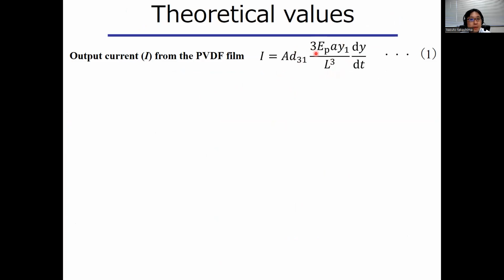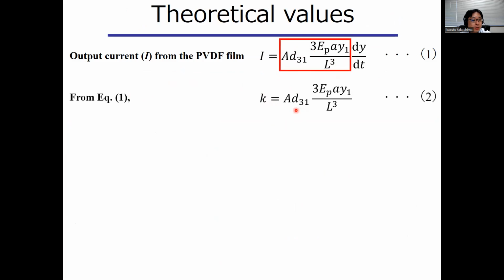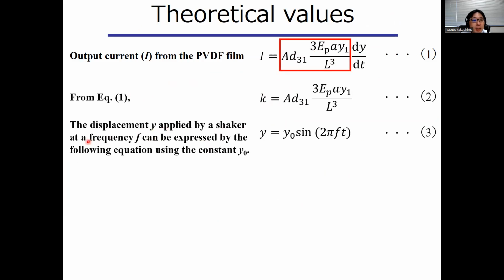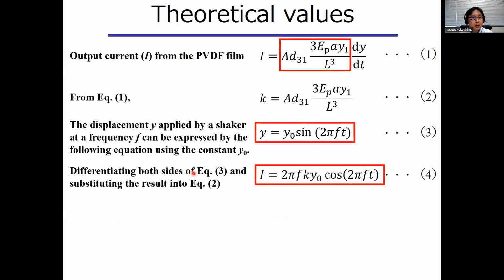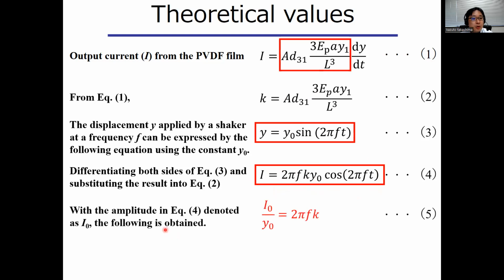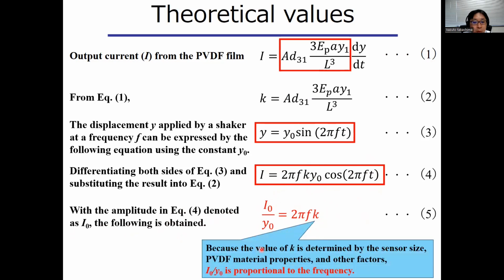From equation 1, the following equation is obtained. The displacement Y applied by a shaker at the frequency F can be expressed by the following equation using a constant Y0. Differentiating both sides of equation 3 and substituting the result into equation 2 gives the following equation. With the amplitude in equation 4 denoted as I0, the following is obtained. Because the value of K in this equation is determined by the sensor size, PVDF material properties, and other factors, I0 over Y0 is proportional to the frequency F.